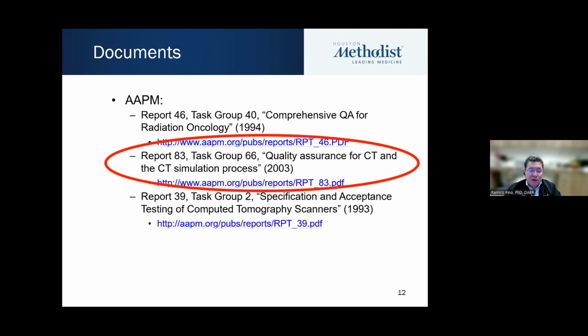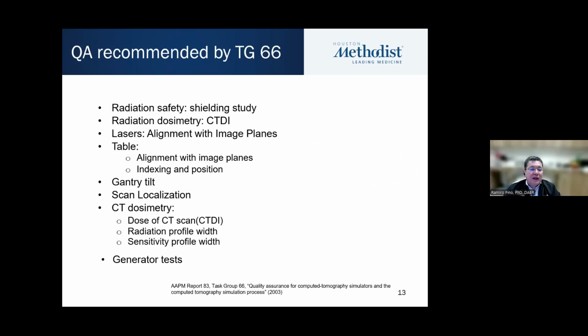For quality assurance for CT simulation, we typically use the Task Group 66 document, which is not fresh anymore. It's about a 20-year-old document, but it's still very useful, and gives a lot of good guidance on how to perform quality assurance on those systems. And the QA recommended starts, obviously, with radiation safety. Once you get your CT scanner or simulator in the room, a shielding study needs to be performed. Make sure that shielding is adequate to protect the public and the employees. A baseline radiation dosimetry needs to be performed, and we need to do laser QA, table QA.